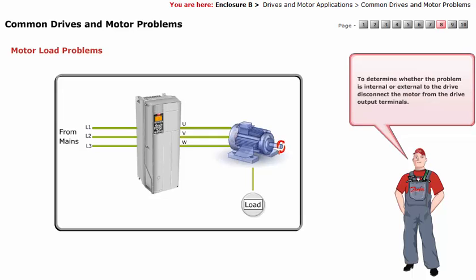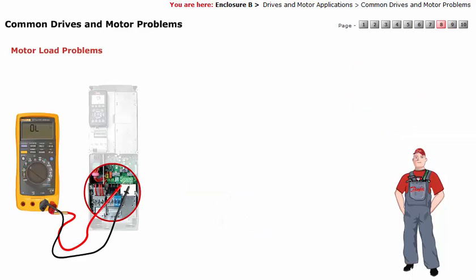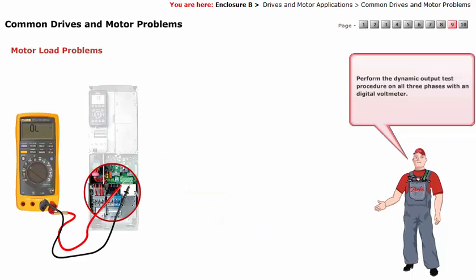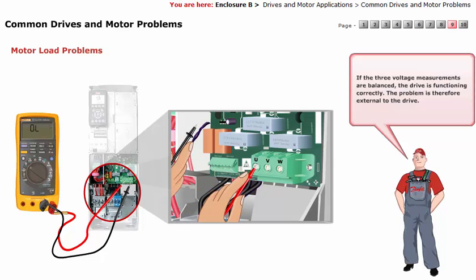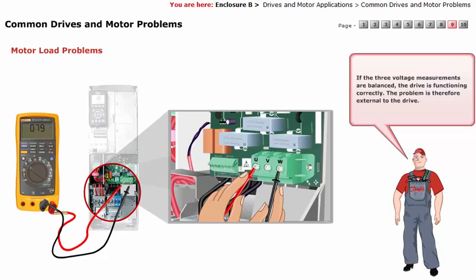To determine whether the problem is internal or external to the drive, disconnect the motor from the drive output terminals. Perform the dynamic output test procedure on all three phases with a digital voltmeter. If the three voltage measurements are balanced, the drive is functioning correctly. The problem is therefore external to the drive.